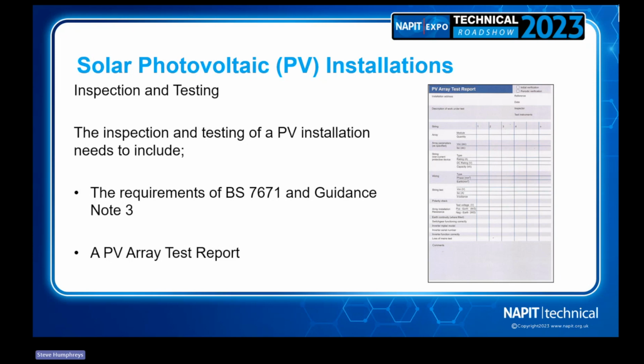But we need to understand the differences in testing the DC side - things like how you do insulation resistance testing on the array and roof, including the cabling. Are we doing a string test, measuring the voltage and current flowing through the array? That would all be captured in a PV array test report like you can see there.